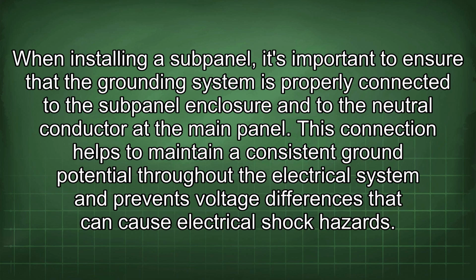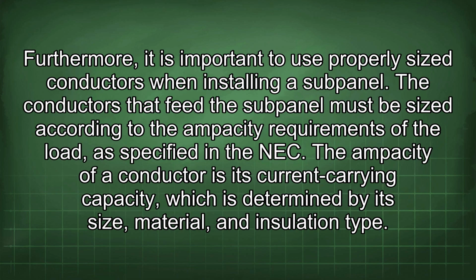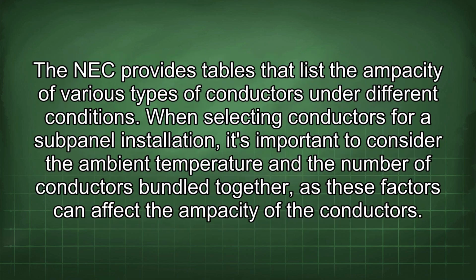electrical shock hazards. Furthermore, it is important to use properly sized conductors when installing a subpanel. The conductors that feed the subpanel must be sized according to the ampacity requirements of the load, as specified in the NEC. The ampacity of a conductor is its current carrying capacity, which is determined by its size, material, and insulation type. The NEC provides tables that list the ampacity of various types of conductors under different conditions. When selecting conductors for a subpanel installation, it's important to consider the ambient temperature and the number of conductors bundled together, as these factors can affect the ampacity of the conductors.